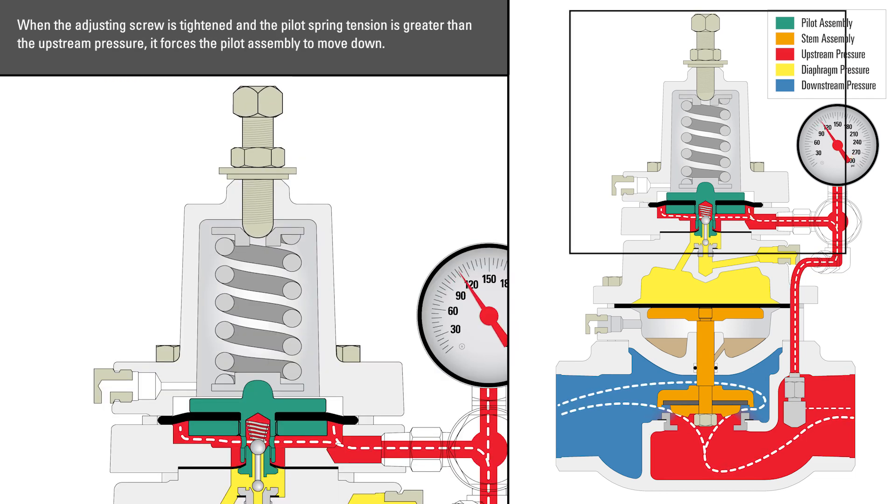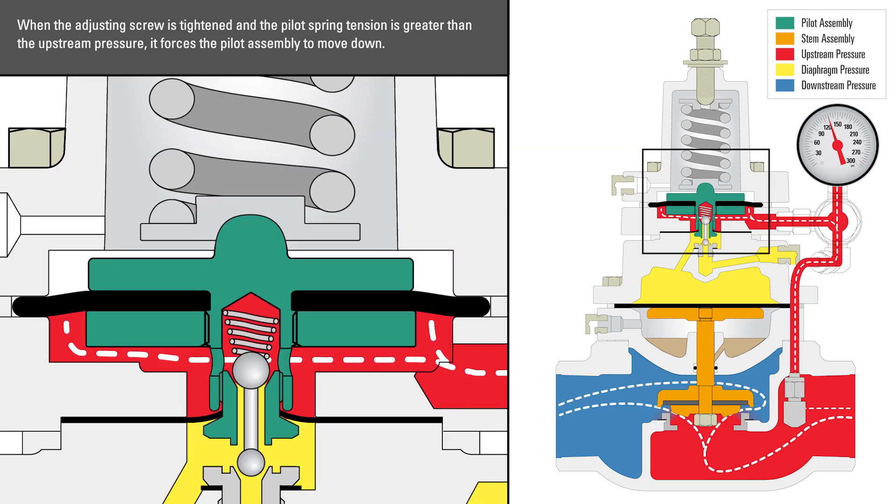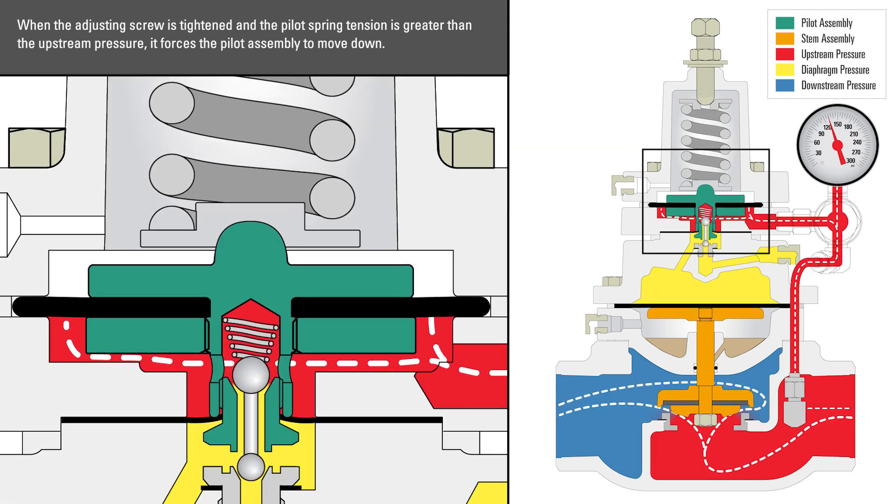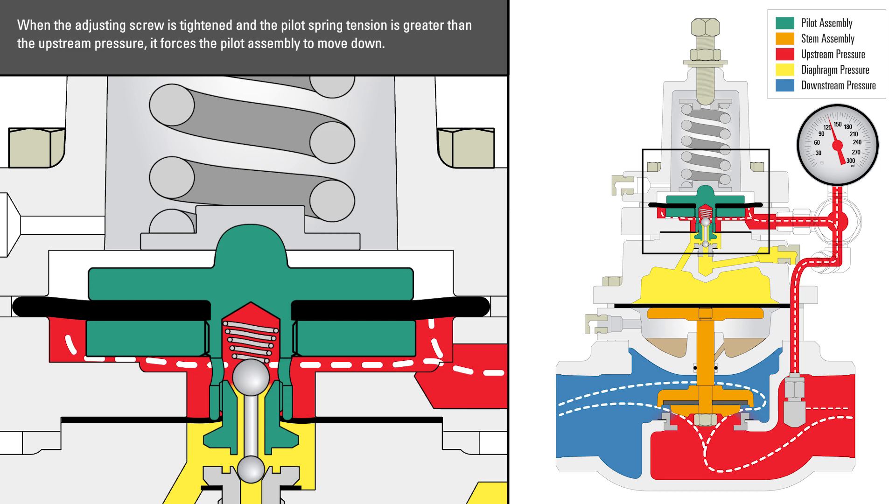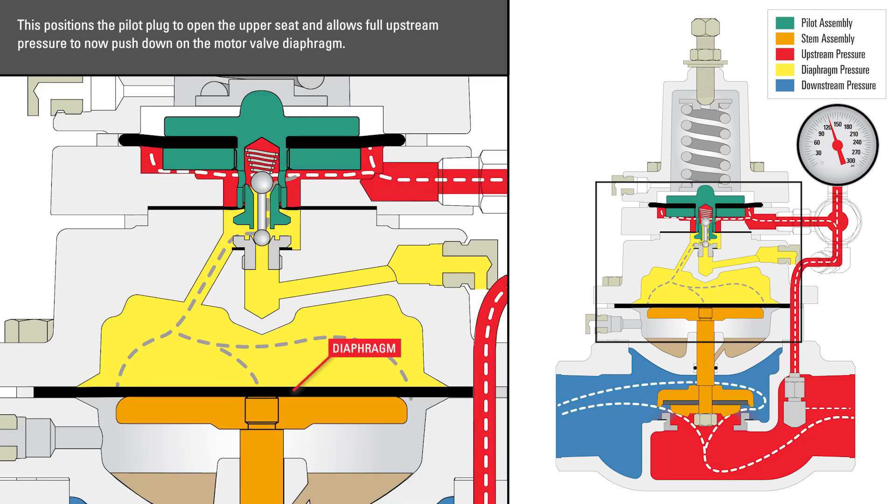When the adjusting screw is tightened and the pilot spring tension is greater than the upstream pressure, it forces the pilot assembly to move down. This positions the pilot plug to open the upper seat and allows full upstream pressure to now push down on the motor valve diaphragm.